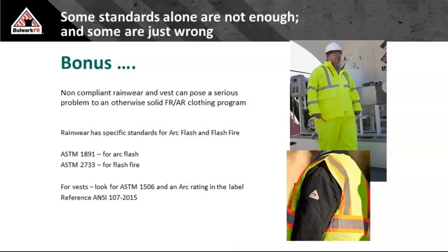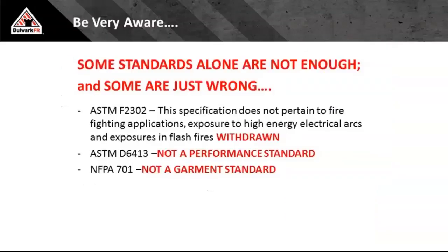Before we get to questions, just a couple quick slides to wrap up. Remember I said we are exposed in general industries to the climates, and in many cases nowadays we're seeing folks having to wear reflective vests to and from job sites, on the job site, whatever the case may be. If you have rain gear, make sure your rain gear is tested to ASTM 1891. That is arc flash rain gear. For our vests, make sure our vests have ASTM 1506 and have an arc rating in the vest. Anything other than that, you are jeopardizing not only your people, but your whole program.